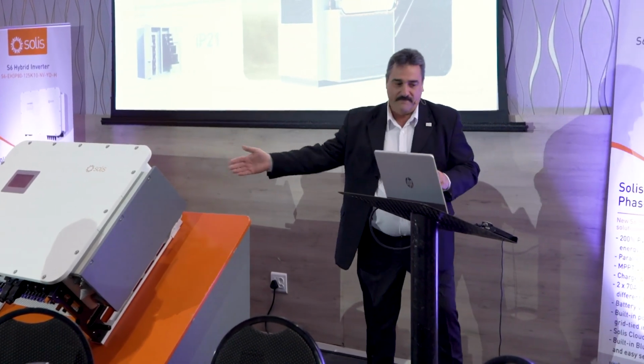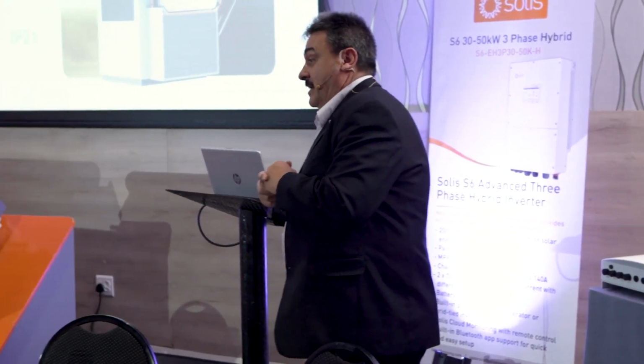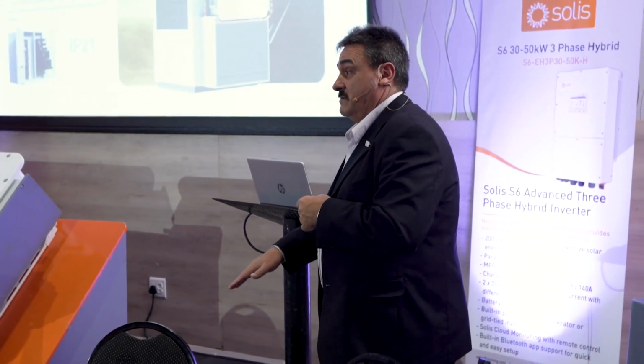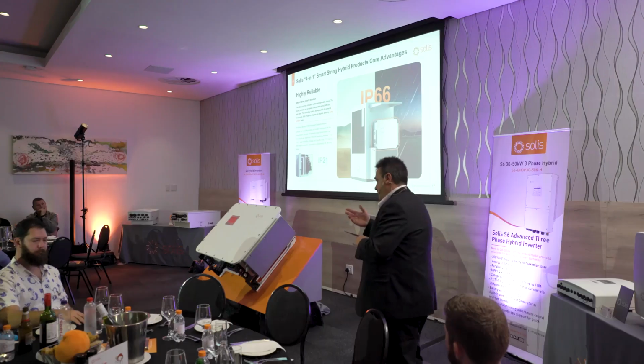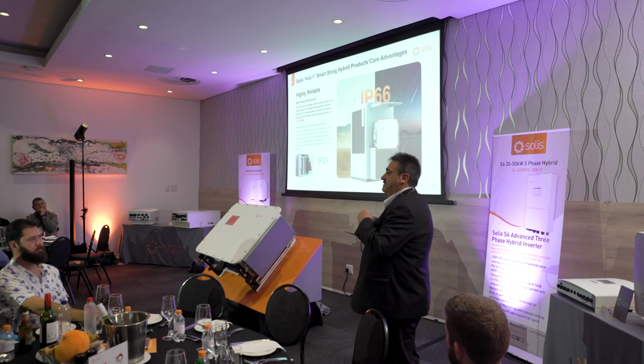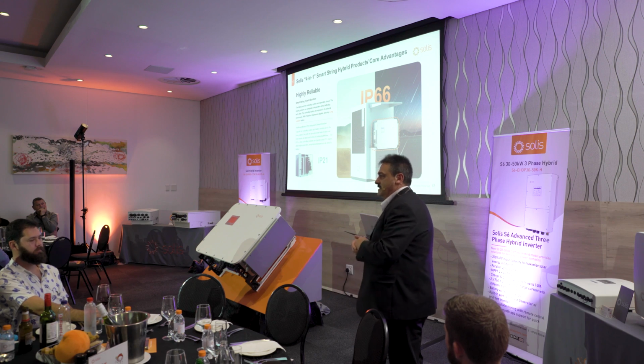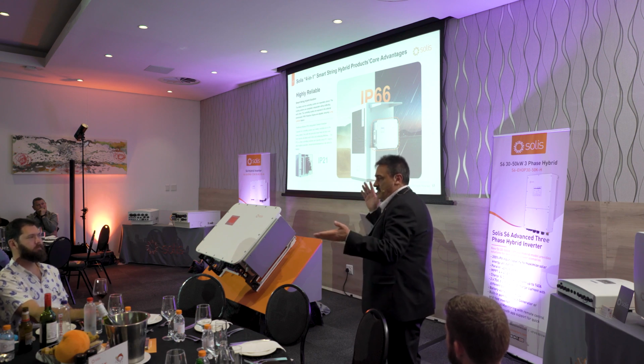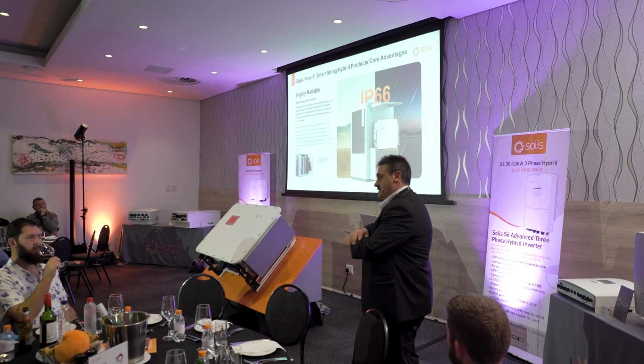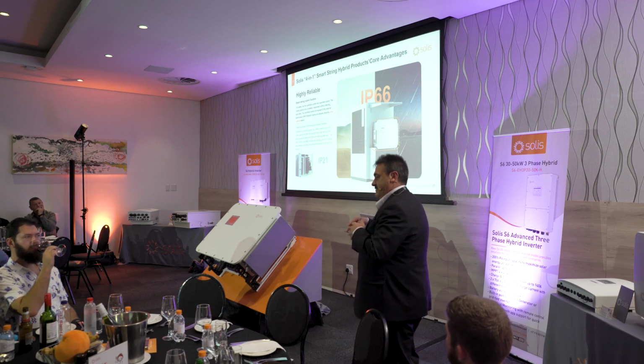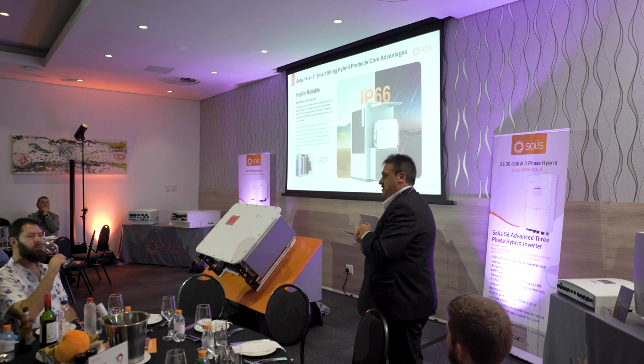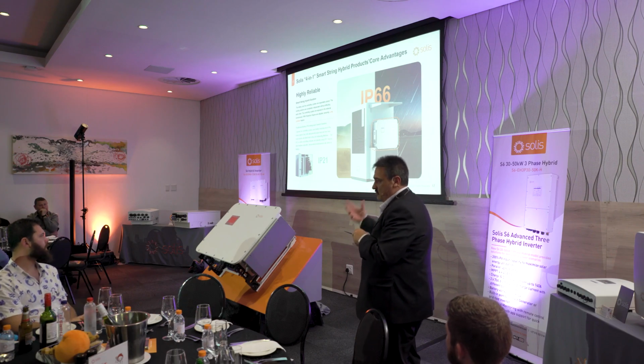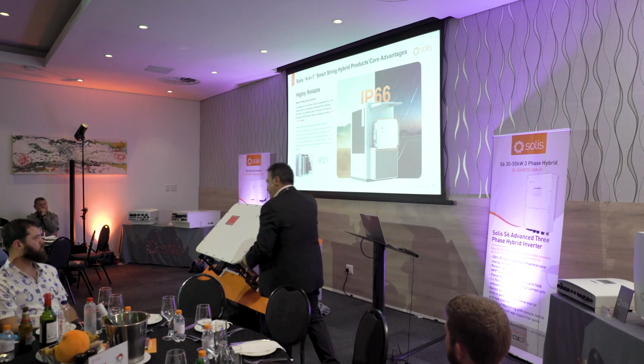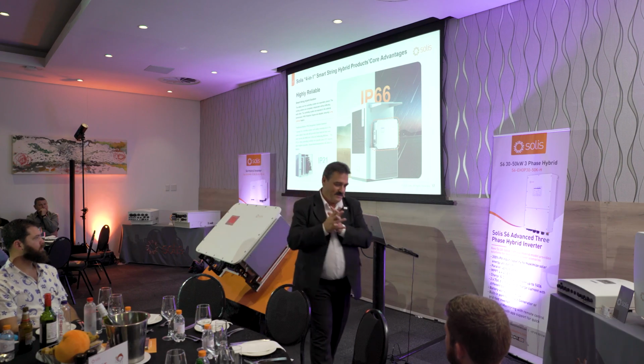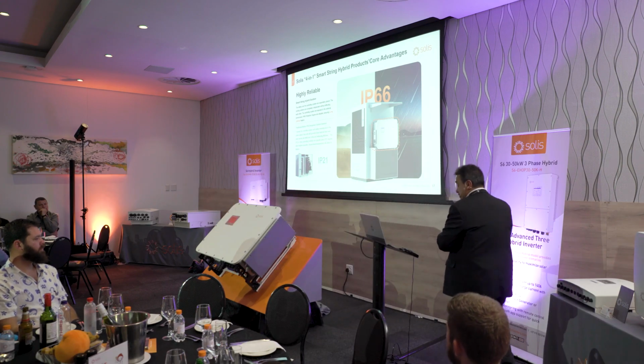Because any product that heats up when it works really hard -- tonight everybody goes to sleep, factory shuts down -- what happens to the inverter? It slows down, it doesn't have that bigger load on it. And if there's air inside, what happens to that air? It condensates, and then it sits on the board. Tomorrow guys come and start up a bunch of things, and then the inverter blows up, and you say, oh, you made another crappy inverter. It's not that -- there's moisture in the system. And electricity and moisture don't like each other. It's like a brother and a sister, they just can't get along.